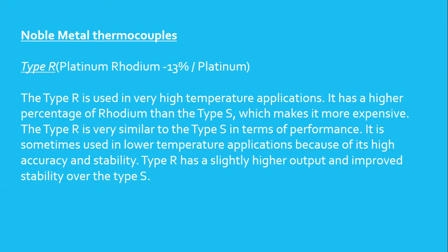Noble metal thermocouples. Type R. The Type R is used in very high temperature applications. It has a higher percentage of rhodium than the Type S, which makes it more expensive. The Type R is very similar to the Type S in terms of performance. It is sometimes used in lower temperature applications because of its high accuracy and stability. Type R has a slightly higher output and improved stability over the Type S.